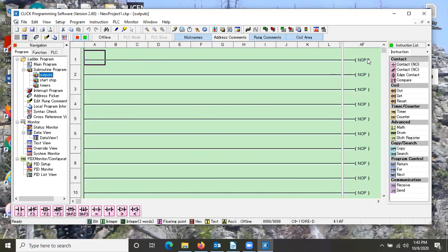because if I go to my output program, you basically have 6 outputs for this. So you will have Y1, 2, 3, 4, 5, and 6. So you'll have 6 output rungs, each of them as an output, and you only use 1 rung per output. Now your inputs or your logic will wind up being ORed, so you'll see a bunch of branches and it will quickly expand out, but that's how you do it.